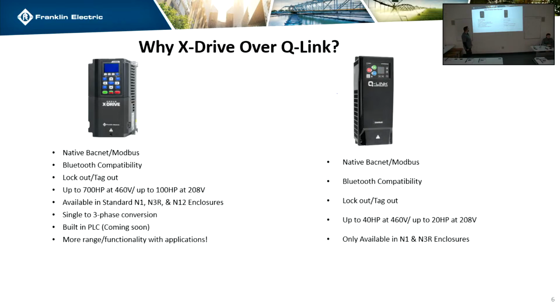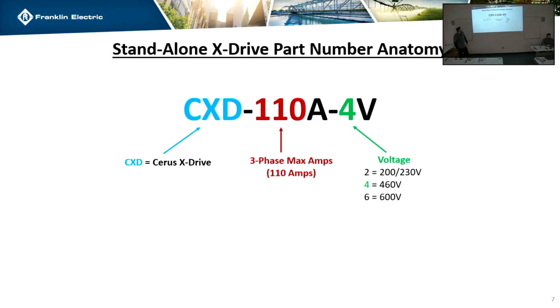So yeah, the big difference between the X drive and the Q-Link is the ranges. The Q-Link was kind of limited in its range. So this has all the functionality in a bigger and more robust package. When you look at the side of the drive, you'll see a sticker that has the part number. CXD just means it's the Cerus X-Drive. The 110 is always going to be your amperage, so you know the rating, and then really the most important piece of information is does it say 2, 4, or 6, so it tells you the voltage of the drive.